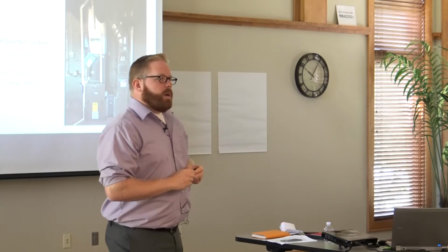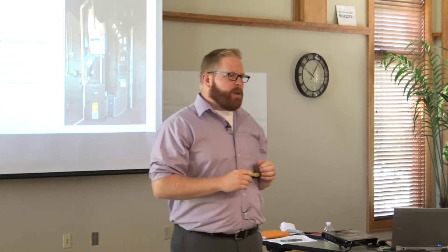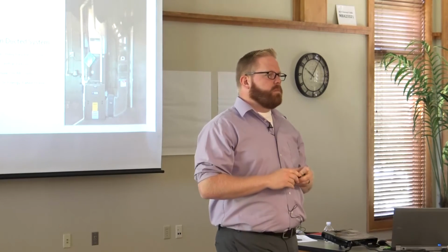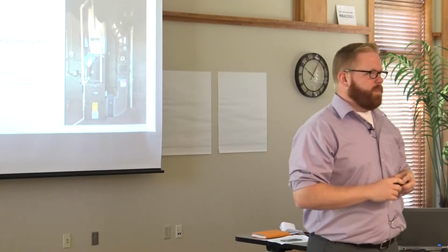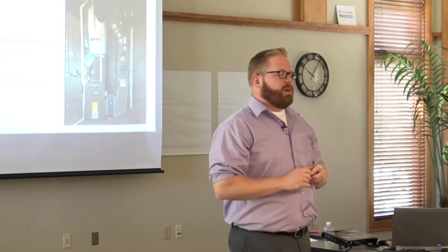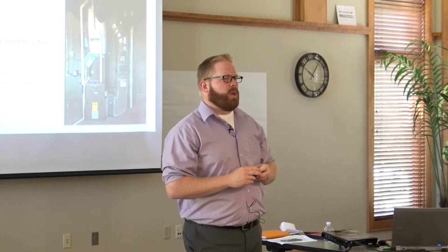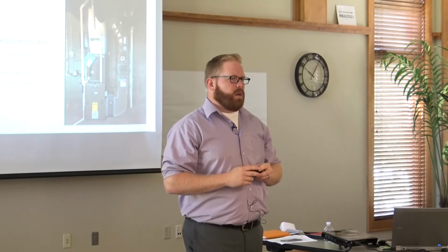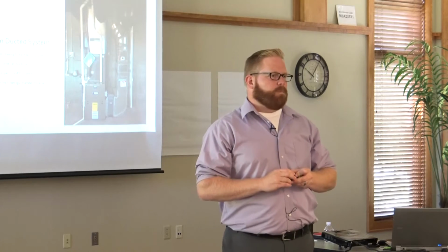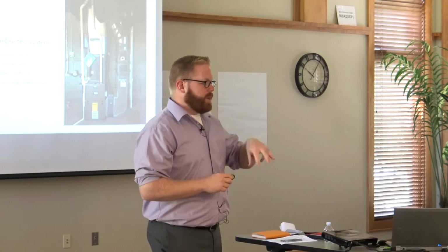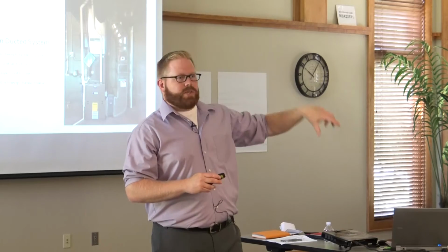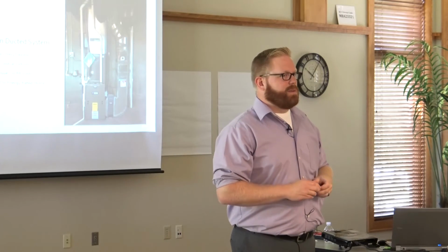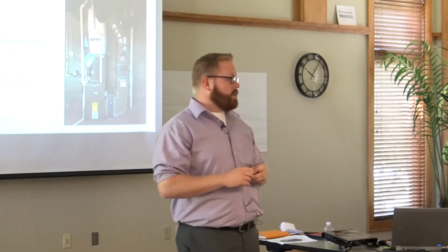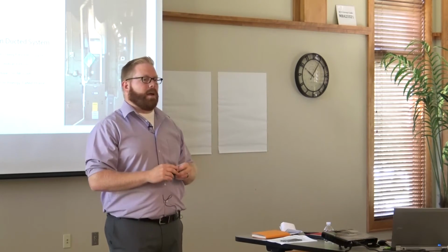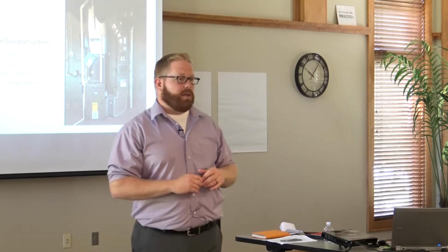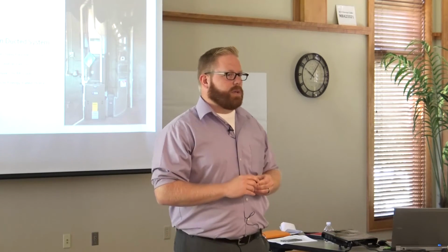Is the state getting to a point where the balance report is required to turn into the building inspector? I believe it is - we perform a balance on every single house. In the commercial world, that's standard. But in residential, how do I trust that my HVAC contractor's installing it correctly? That's a good question. All municipalities, all subdivisions are a little different, every county is even a bit different. But to my knowledge, a CFM or air balancing report is needed for most municipalities to pass inspection.